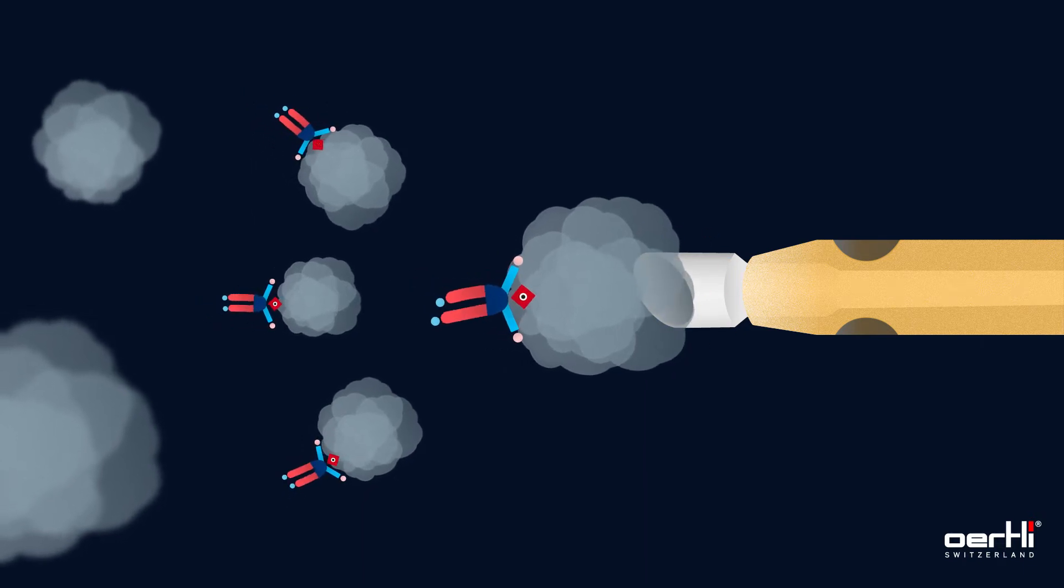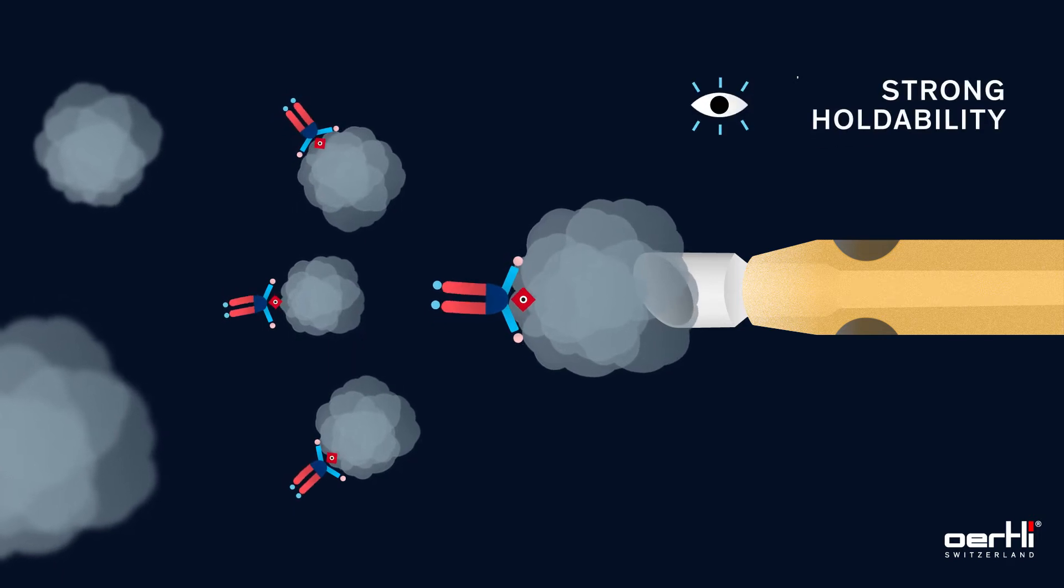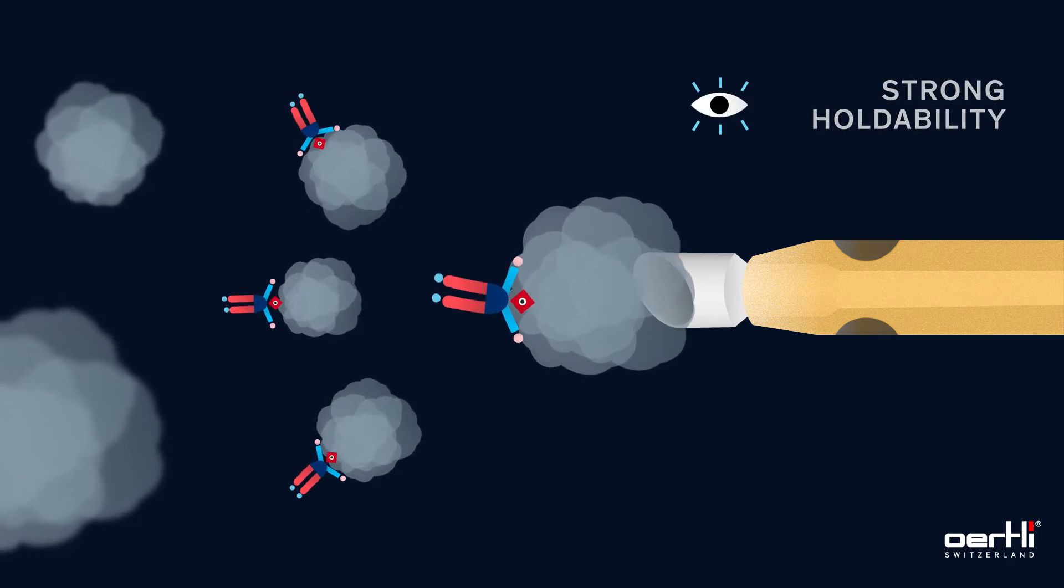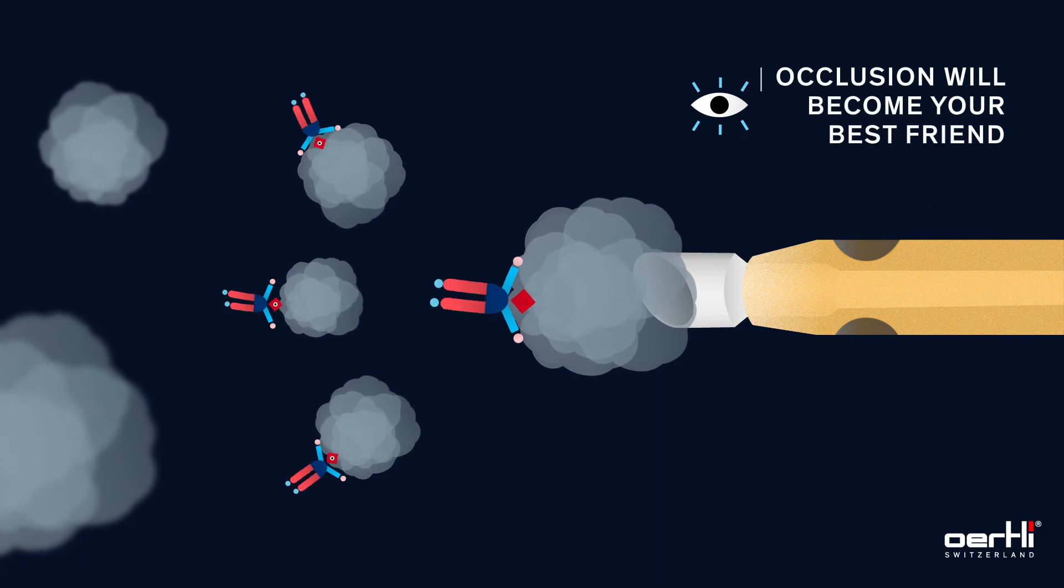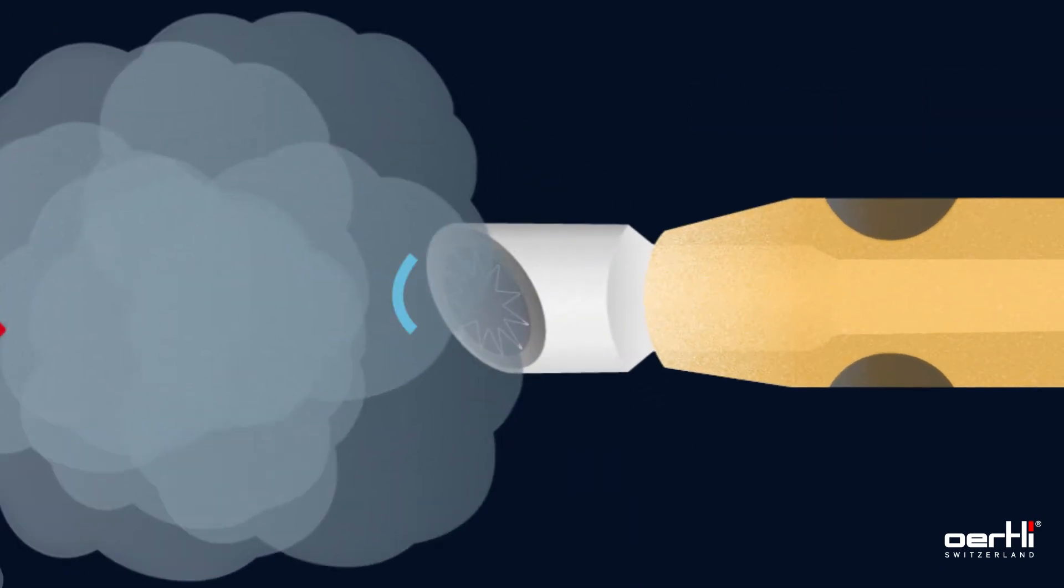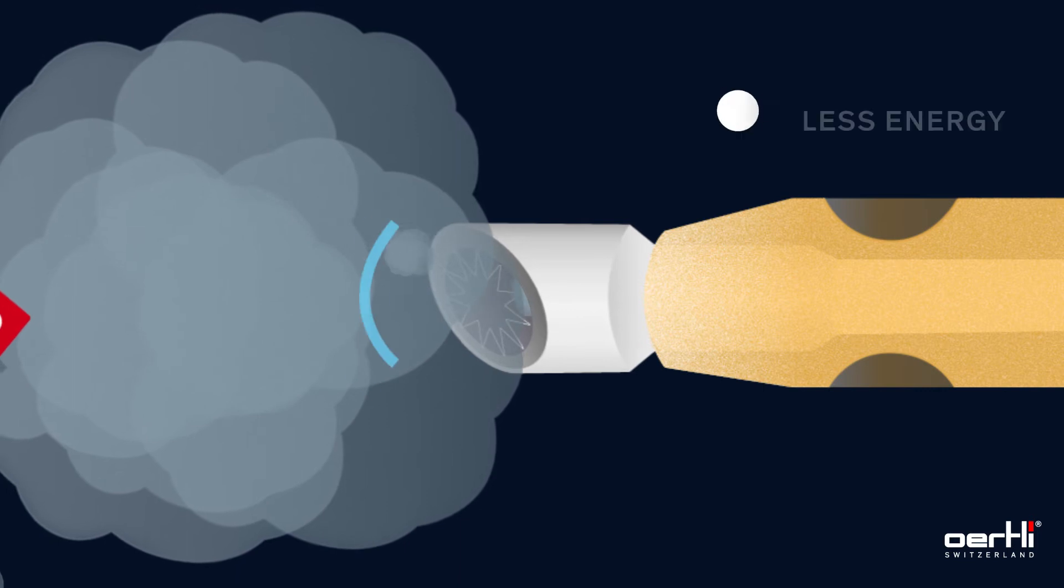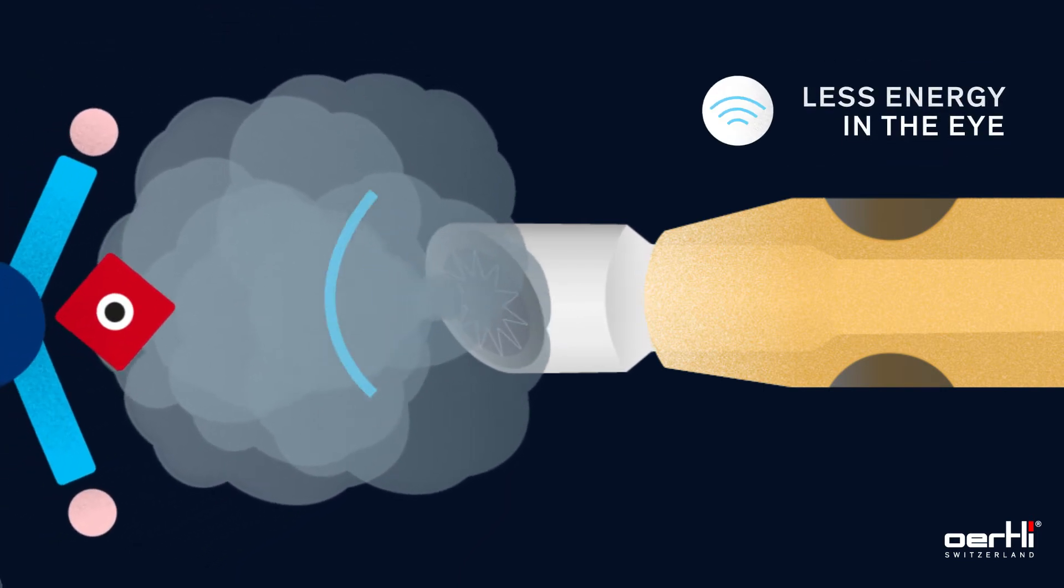Our easy tips hold fragments firmly at the tip with strong holdability. With easy phaco, occlusion will become your best friend. Thanks to the strong holdability and the longitudinal movements of the straight form tip, the ultrasound is applied directly into the fragments after occlusion.